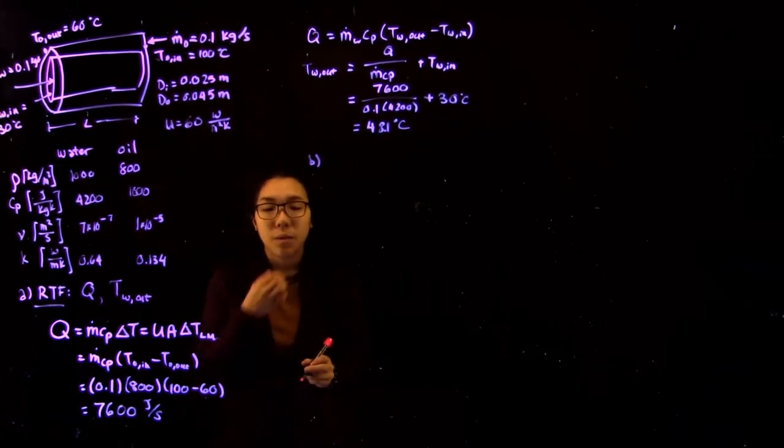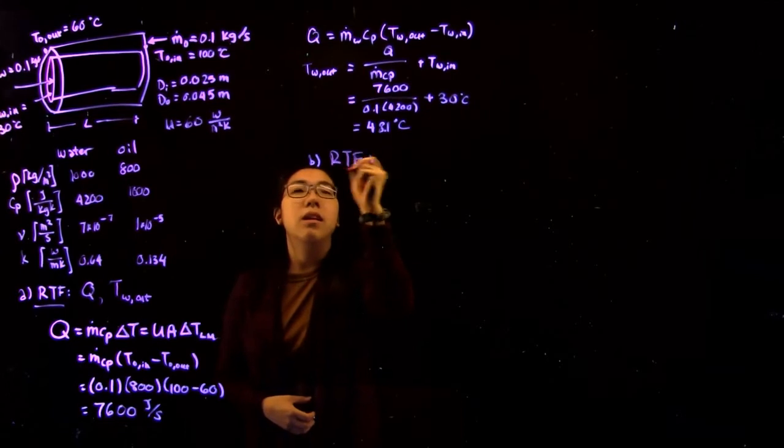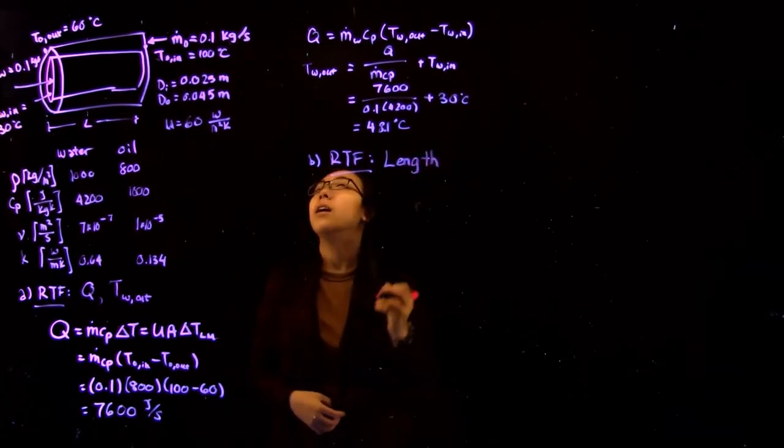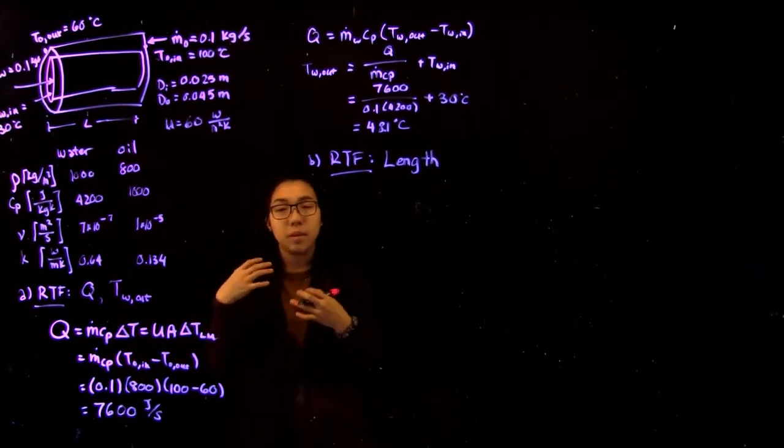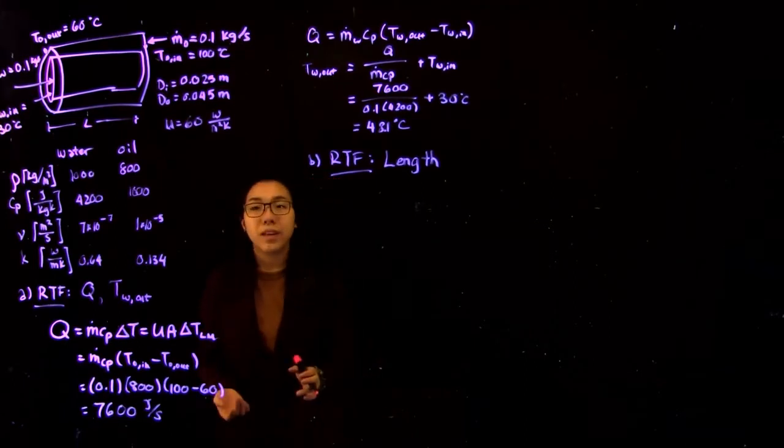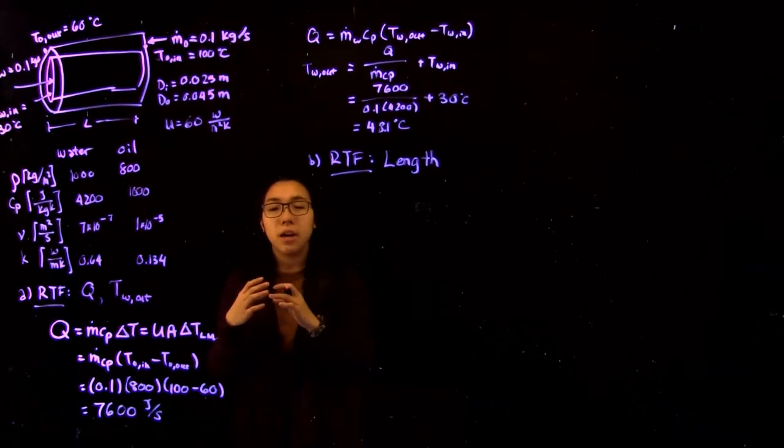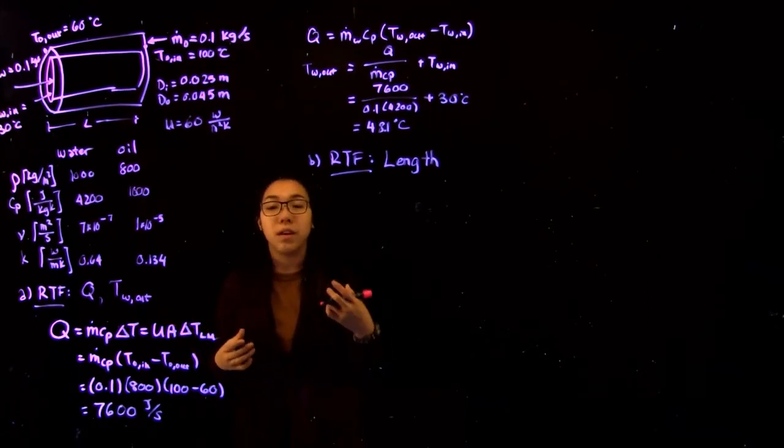So the next part of this question, the next thing we want to calculate, is the length that is required of this heat exchanger. Essentially how much heat that's transferred has to do with the surface area of the two fluids that are in contact. The surface area is just defined as the diameter of the inner shell of this heat exchanger times the total length, because that gives us the surface area of a cylinder.